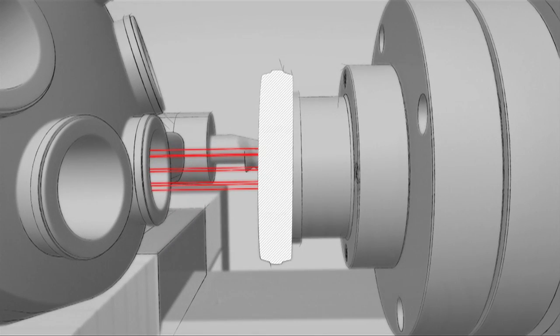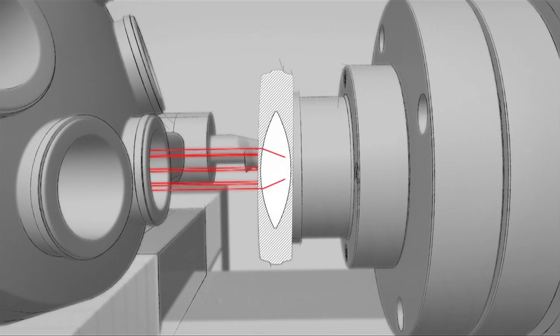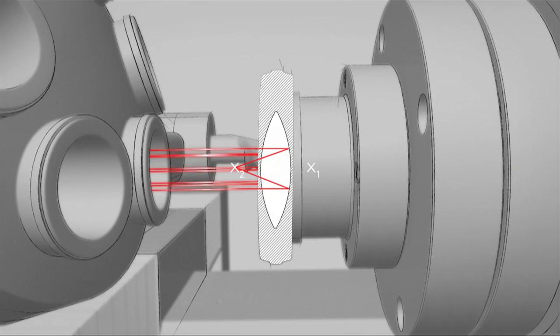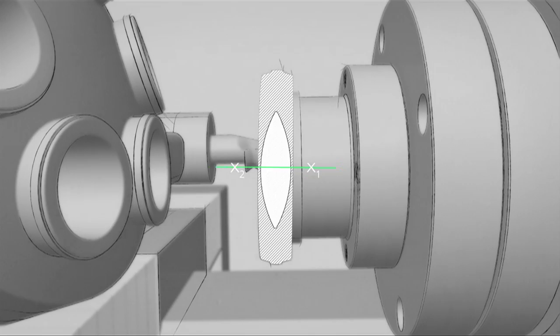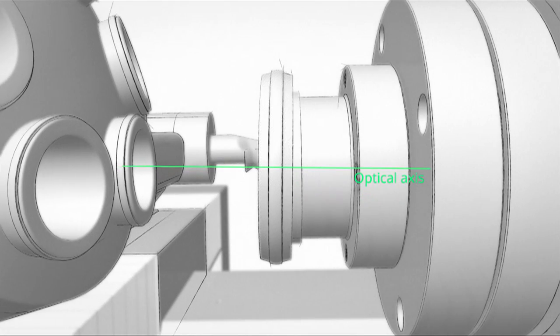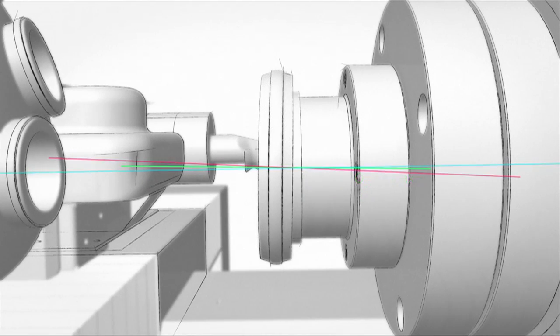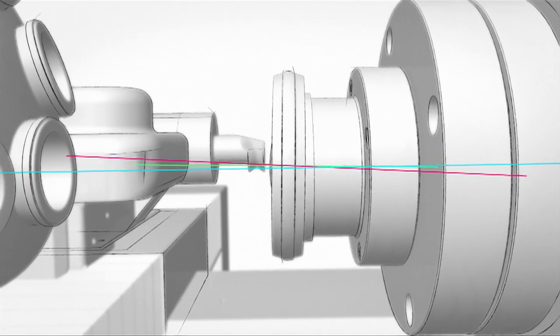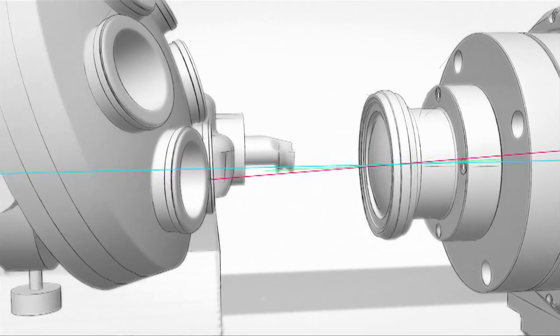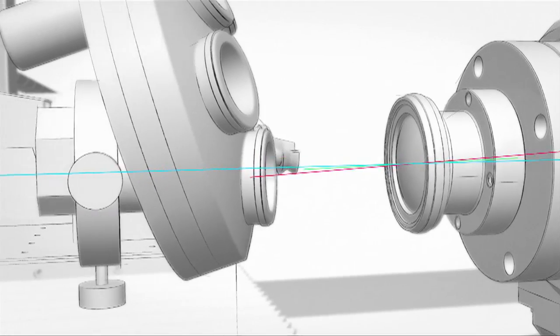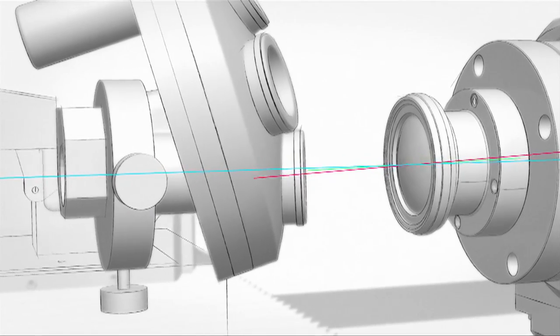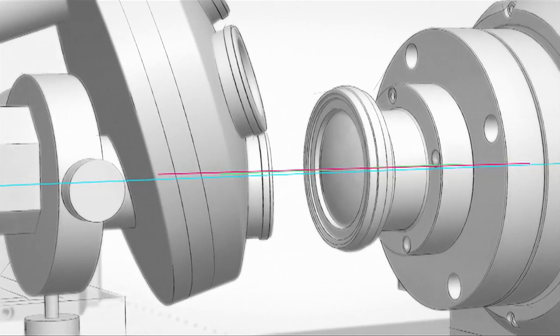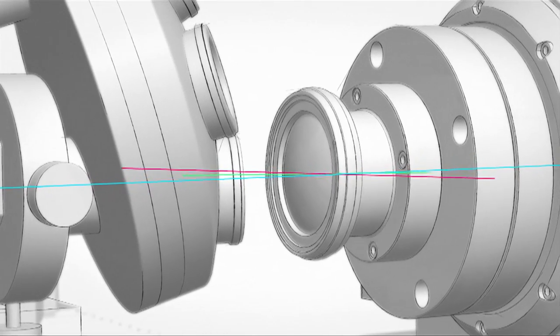It measures the centre of curvature of the front side of the lens X1 and the rear X2. In the next step, the software uses the centres of curvature to determine the position of the optical axis. This is also skewed towards the spindle.